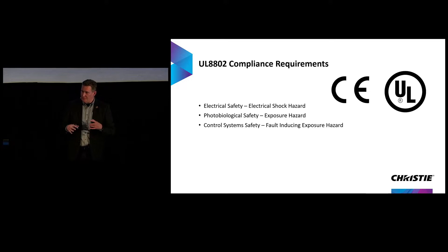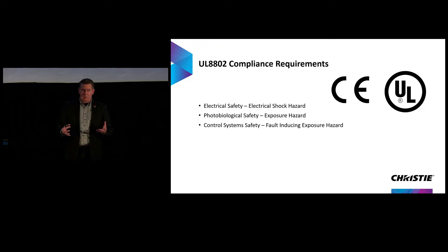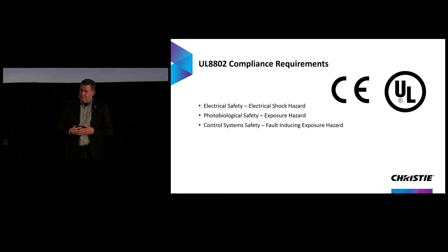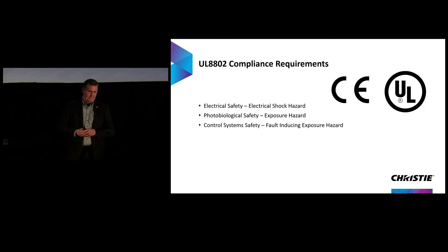The third piece of certification testing you want to make sure has been done is control safety. Basically, control safety asks: if a fault occurs somewhere in the system, could you end up violating the photobiological guidelines? They look at fault testing and verify that if there's a failure in any of your circuits or software, the system will degrade gracefully and not end up in an overexposure situation.